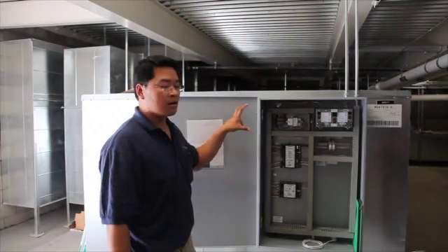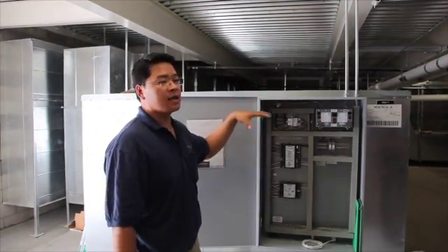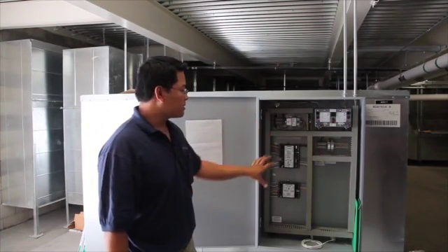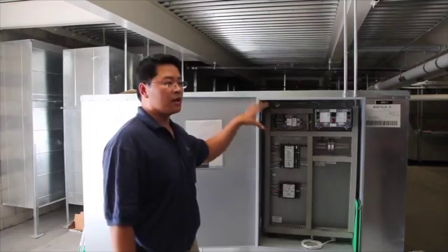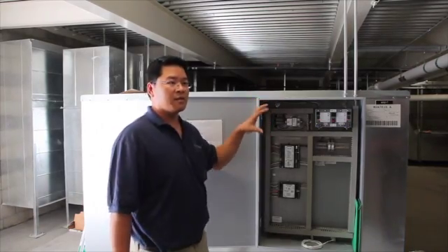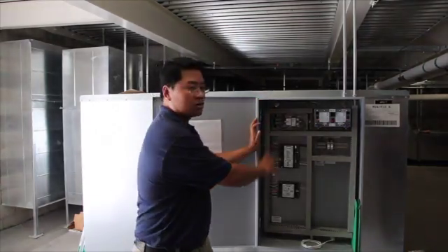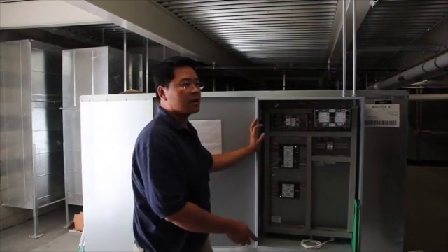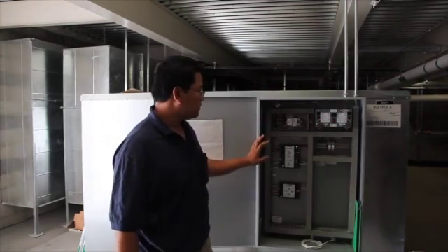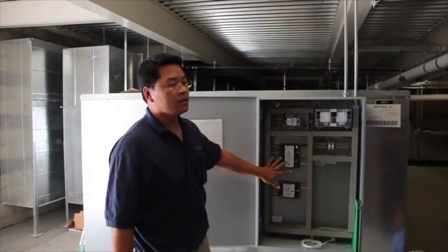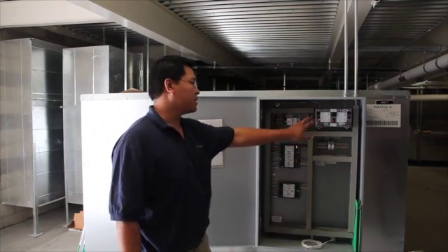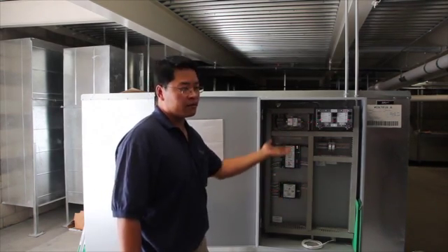And when it trips those particular hard latches, you have to manually reset here. You can't do that over the computer. The purpose of that is just to make sure you know that hardware has tripped on something that is non-essential to the computer. Maybe some discharge temperature is not working or something like that, or a fan fail.